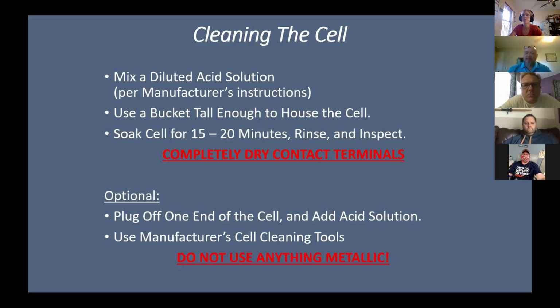All right. The bottom in red, do not use anything metallic. Do not scrape the blades. Anything that you do that will scrape the blade can compromise the life of the cell. Because if you look at inside of a cell, you've got a whole bunch of blades. Those blades are titanium. The titanium itself is impervious to any kind of chemical attack. On the surface of the titanium blade is a coating that's called ruthenium oxide. Ruthenium oxide is a precious metal coating, and that's the coating that sacrifices itself for the chlorine generation process. So anything that you do that's metallic that'll scrape that ruthenium oxide coating is going to allow water to get into the titanium. It's going to get underneath the ruthenium oxide coating and cause delamination, cause premature cell life in your cell. Okay, so do not scrape it with anything metallic.